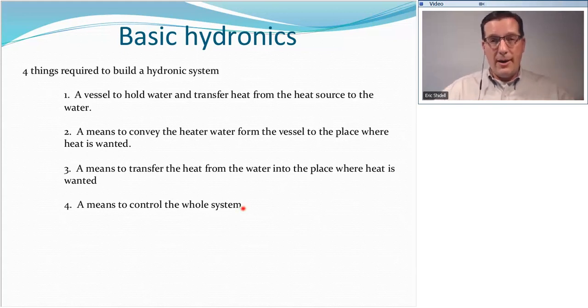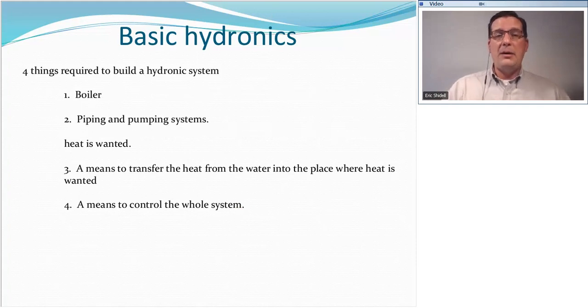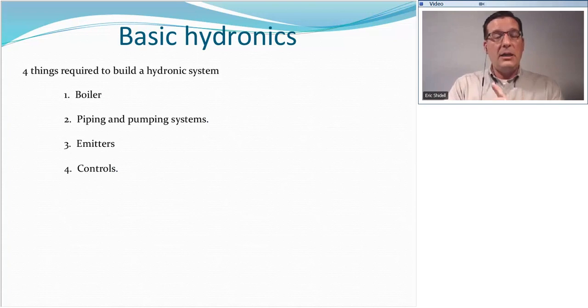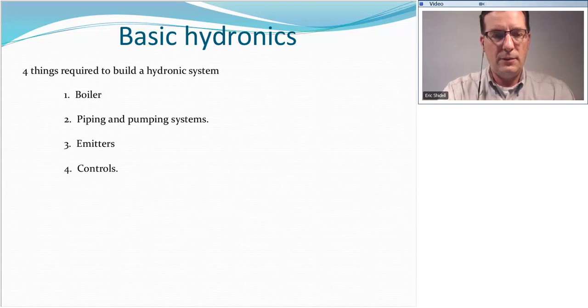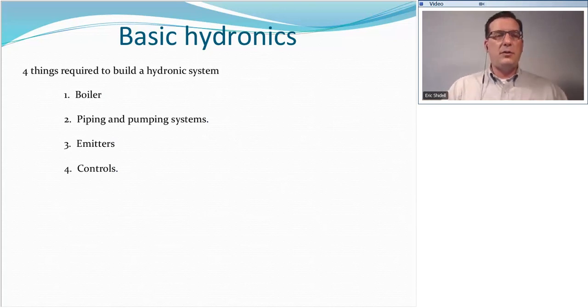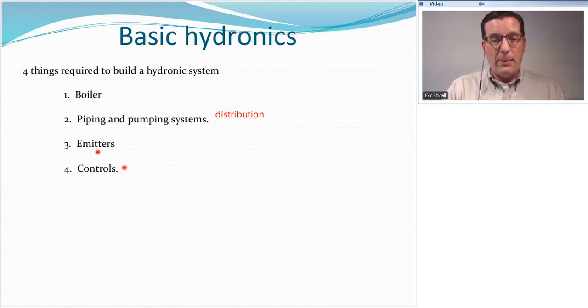Now, this is a pretty broad definition. There's lots of different ways we can assemble these four components to create an active hydronic heating system. Most of the time, here's what that means. Number one is going to turn into a boiler. That's the vessel that transfers heat from a heat source, such as a gas flame, oil flame, coal flame, wood flame, into the water. That's the boiler. Some means of moving that water out of the vessel and into someplace, that is called our piping and pumping system. There's another name for that that I want you to write down, and that is distribution. Distribution. Piping and pumping systems, also known as distribution system. Next, we have to have some way to get that heat out of the water into the place where we want it, and that is the emitters. And finally, something to control the whole system, and that is usually our electronic controls. Now, back in the olden days, those would be manual controls, but today, most of them are electromechanical and even electronic.